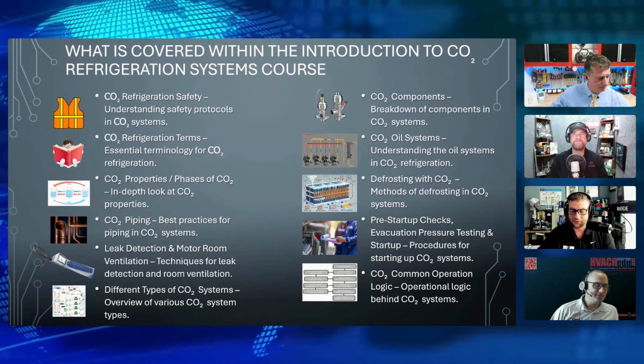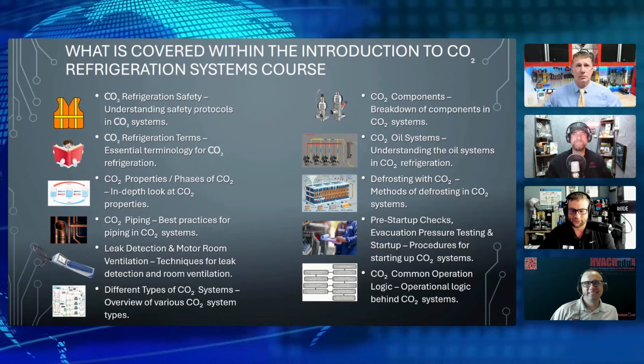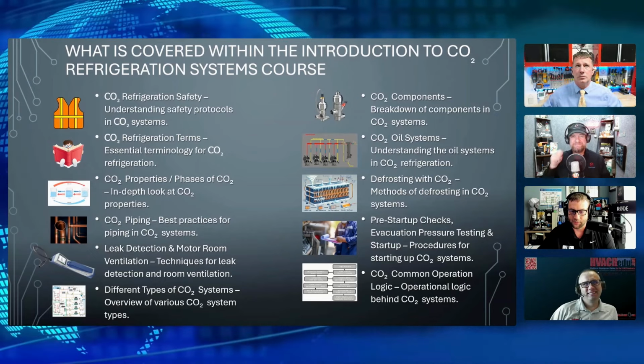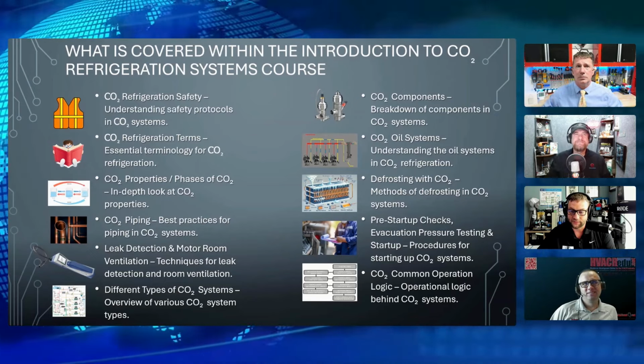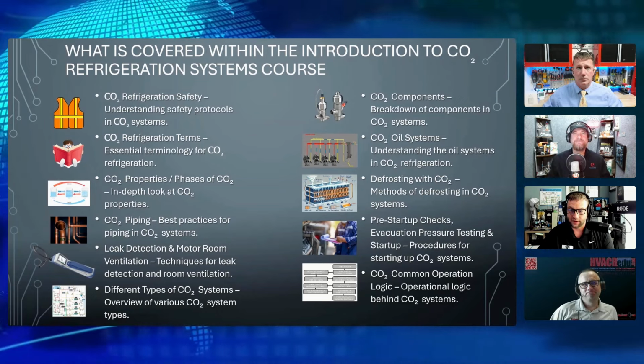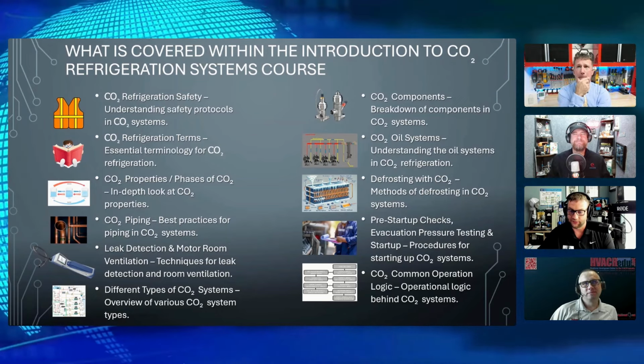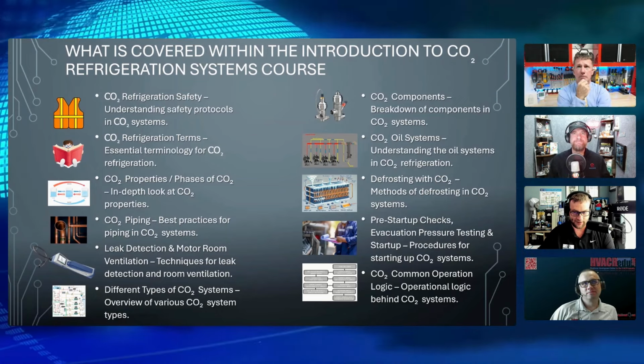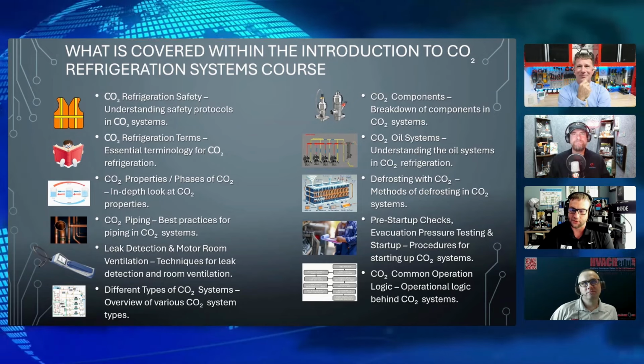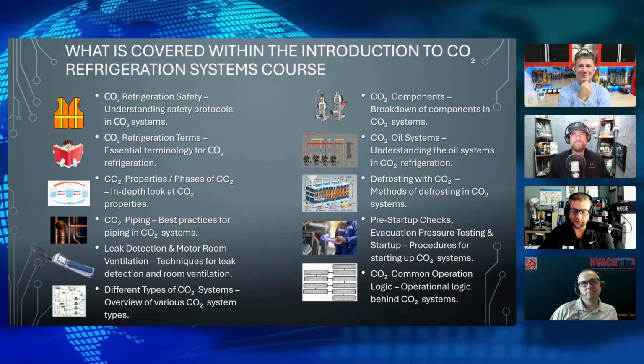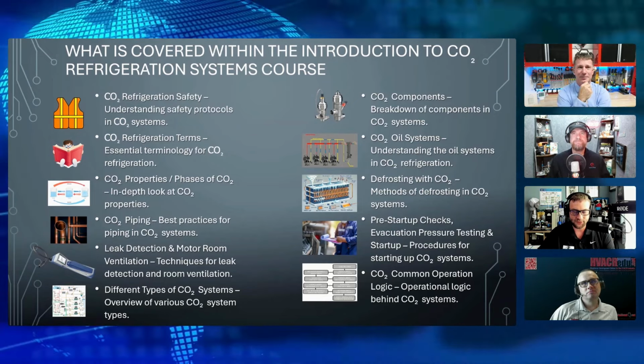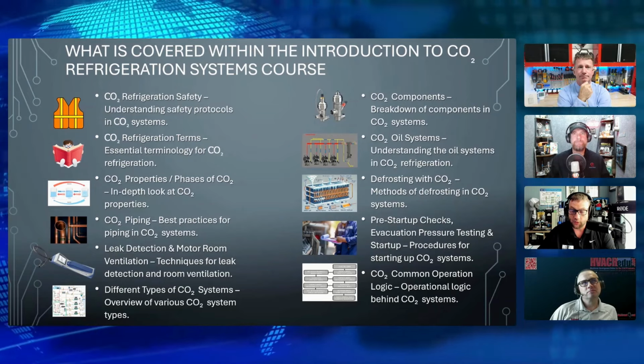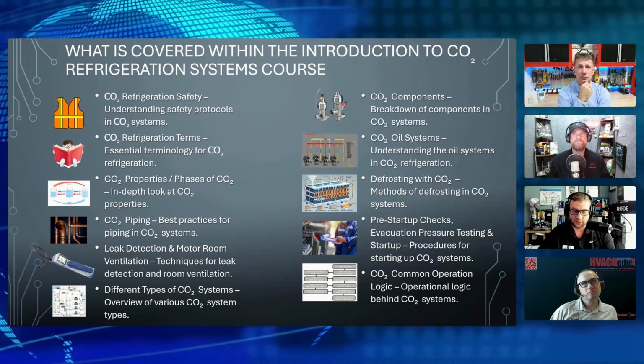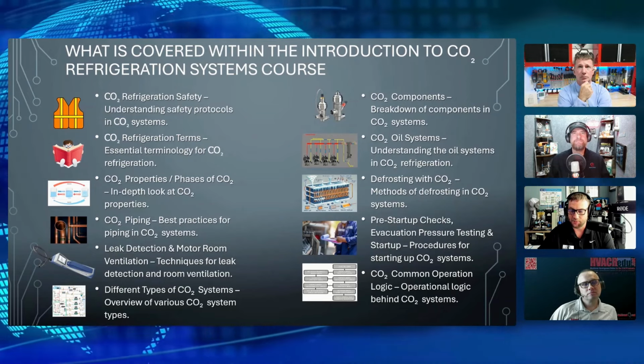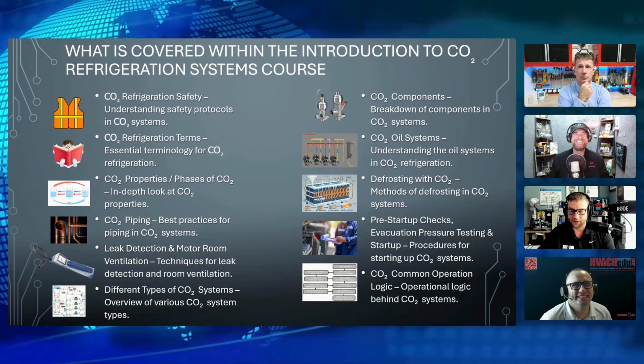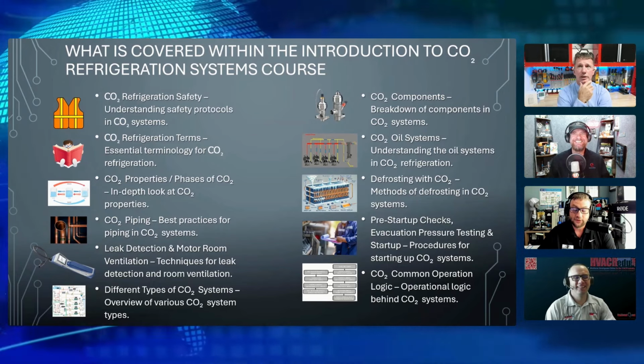Besides the three little magic things that make this thing work, it's basically DX refrigeration. It is. We still have expansion valves. We still have compressors. We still have condenser-type things called the gas cooler. We still have the major components of the system. It just differs a little bit. Knowing, with the high pressures, once again, the critical point. I know I'm going to keep beating this horse to death, but I have to talk about it because it's the main component of this. That's what we're here for.